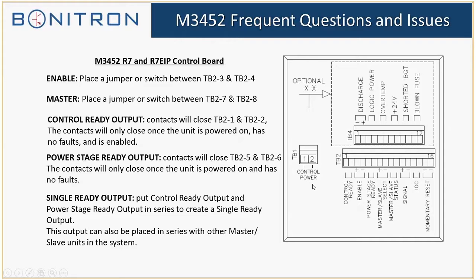TB1, this is the control power. This will be how you power the 3452 and its logic. In order to get this unit to operate properly, the question I get most often is about the enable. It's just very common. They get power to the unit and they expect it to work straight out of the box, but our units do not become pre-enabled or come with the jumpers already installed. A lot of our customers want to be able to remotely control these and bring these on and off a common bus, just depending upon their setup. So the enable is controlled on terminal strip 2, terminals 3 and 4. The unit must be enabled for it to function.